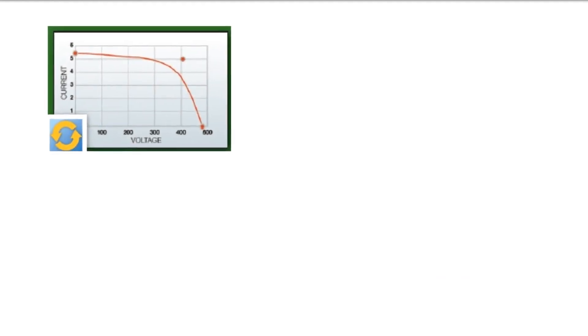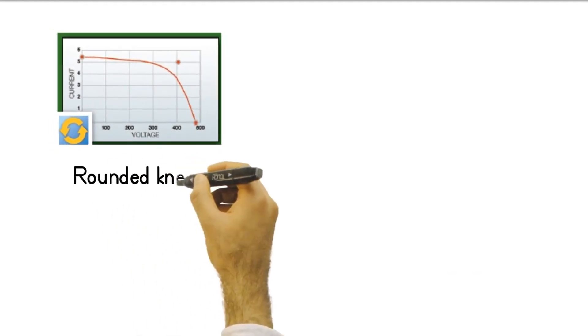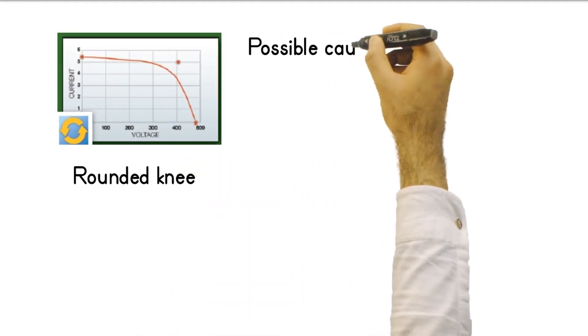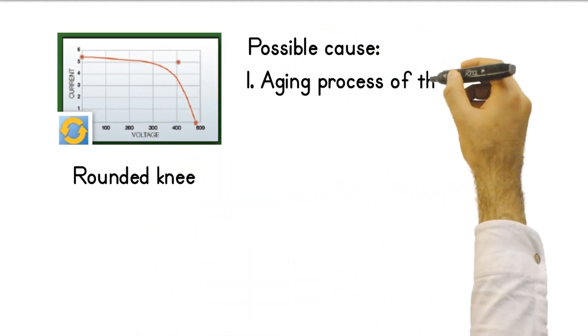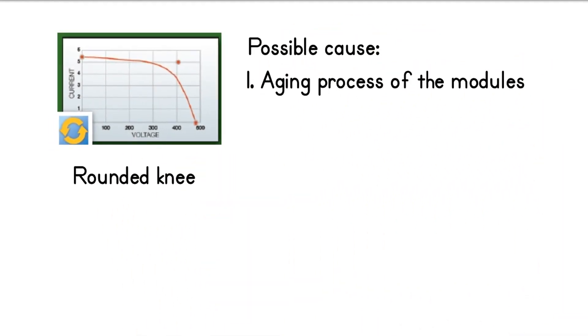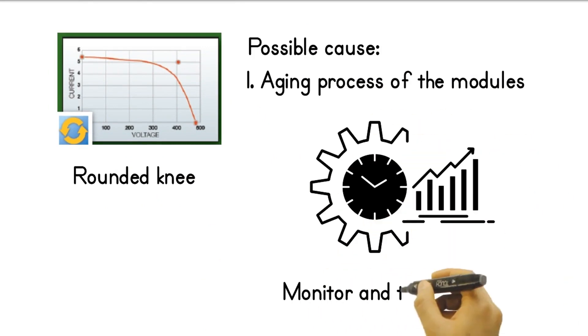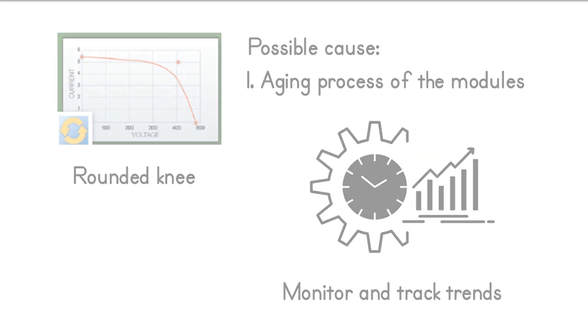The fourth type of deviation is a curve with rounded knee. It is most likely caused by the aging process of the modules. This can be identified by monitoring the string over time and tracking trends.